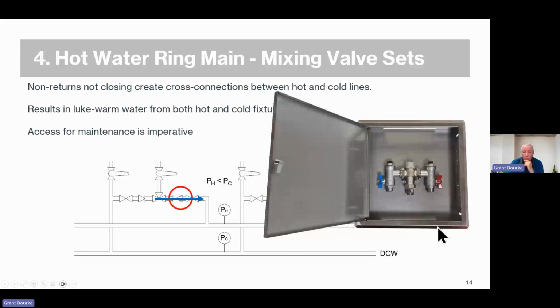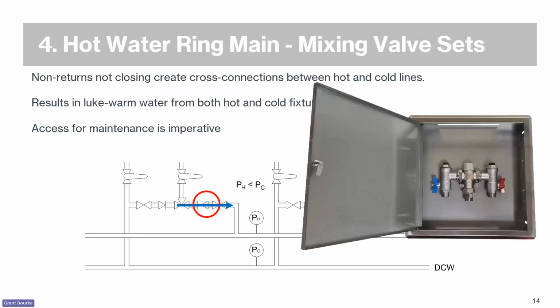Many suppliers will do a nice little compact valve kit. That's one from Waterware that's got isolation valves, non-returns, swivels, mixing valve, and they'll sell them to you in a nice little cabinet. So if you can't get the valves under the floor or somewhere in the attic, you need to be talking to your client about where you can locate these cabinets that's not going to upset them.